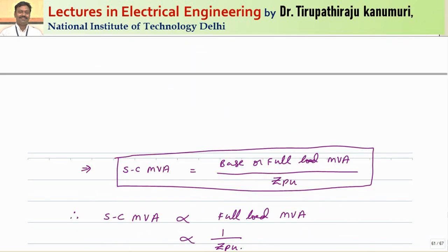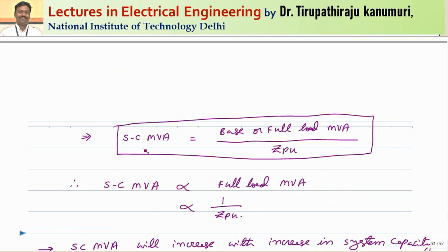Short circuit volt-amperes — or short circuit MVA in practical terms — equals base or full load MVA divided by Z per unit. From this, we can tell that short circuit MVA is directly proportional to the full load MVA, or the rated capacity of the system.